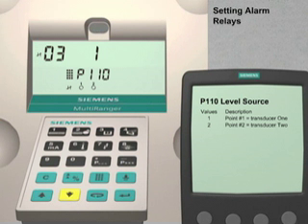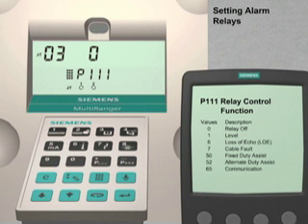Push the down arrow key to scroll down to index number 3. Press the next display key three times or until P dash dash dash appears in the parameter number field. Enter 111. Parameter 111 sets the relay control function. The display is indicating that index number 03 currently has a value of 0, meaning that relay number 03 is currently turned off.